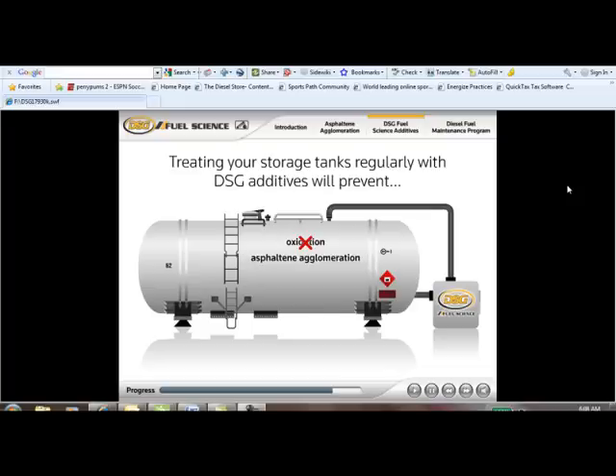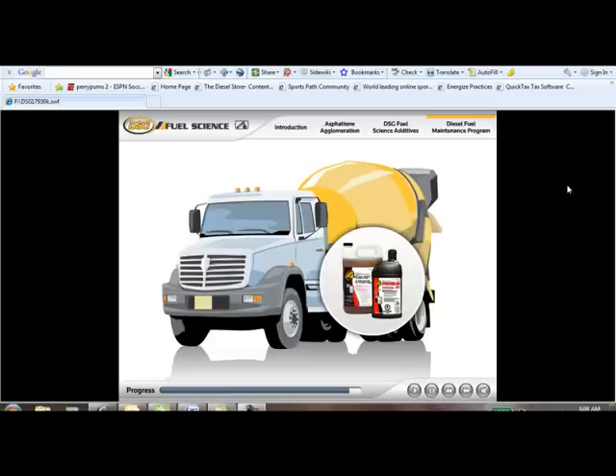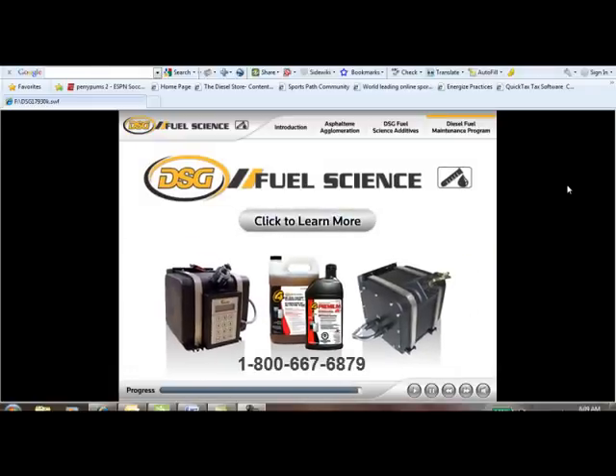Treating your storage tanks regularly with DSG additives will prevent oxidation, asphaltene agglomeration, condensation, and contamination. If fuel is stored more than 30 days, it should be polished with a DSG fuel polishing system, which periodically circulates the fuel to remove water and organic deposits. Fuel pumped into your vehicle or equipment tanks should also be treated with DSG additives — done manually or through automated onboard dispensers. This simple and cost-effective fuel maintenance program can save you untold costs and disruptions to your business. Click on the link.